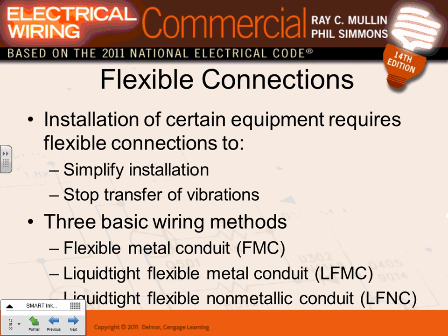Conduits are divided into two categories: flexible and non-flexible. Everything we've talked about - EMT, rigid, PVC - is non-flexible. Flexible conduits have three types: flexible metallic conduit, liquid-tight flexible metallic conduit, and liquid-tight flexible non-metallic conduit. It doesn't take a genius to understand that anything with 'liquid-tight' is used in wet locations. Anything without 'liquid-tight' is for dry locations only.